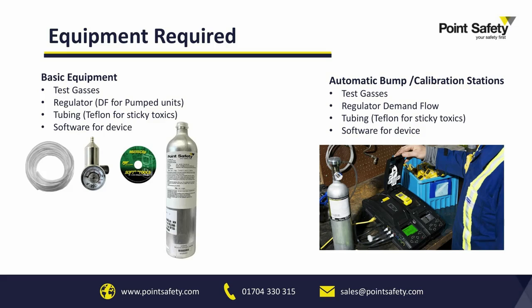Also, bearing in mind the types of gases that you are detecting within that meter, they may require different types of tubing. PVC tubing is suitable for a lot of gases, but some of the sticky toxics, your chlorines, chlorine dioxides, will require Teflon tubing in order to ensure that the reading and the concentration of the gas going through the tube isn't distorted.